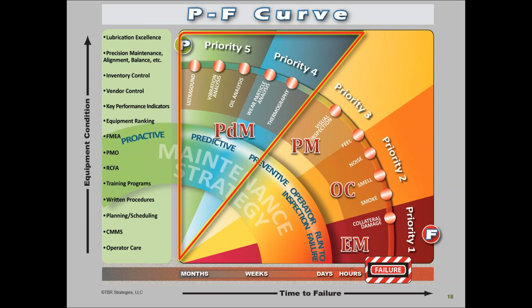This uses some of the technologies of thermography, wear particle analysis, oil analysis, vibration analysis, etc., because they could give us longer lead times of detection. So we're using these technologies to monitor changes in conditions by comparing where we're at against known engineered limits. We know what it's supposed to be, we know what it was tracking, but now it looks like it's starting to get out of control.